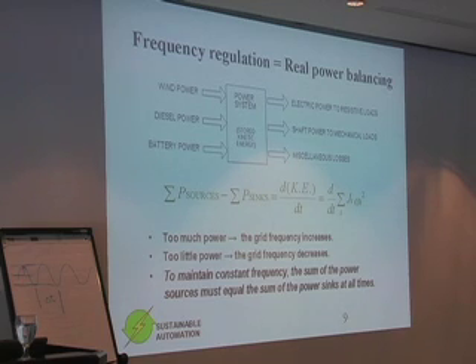You can think of all the rotating machines, whether they be in the generators, like the diesel generators or the wind turbines, or the loads, like pumps, washing machine motors, whatever. They all have spinning mass, they all have inertia. So the imbalance in energy gets stored, the stored energy of all those things will increase, and you'll have a corresponding increase in system frequency. So the problem of frequency regulation is a problem of balancing real power at all times.